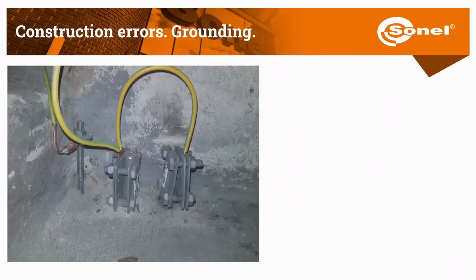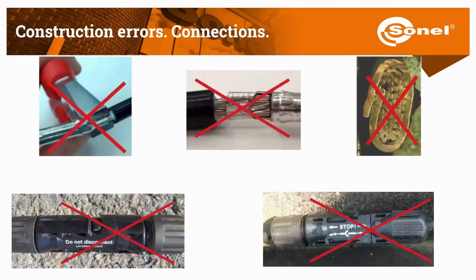Here we can see how the user is making problematic grounding, connecting rods because of not enough efficiency of the earthing resistance, and how he connects the cables without connectors. This can be problematic in the future, because we are supposed to make sure that everything is connected through proper connectors. The pressure on a loose cable can cause a big increase of resistance, or even damage the whole continuity of the cable.